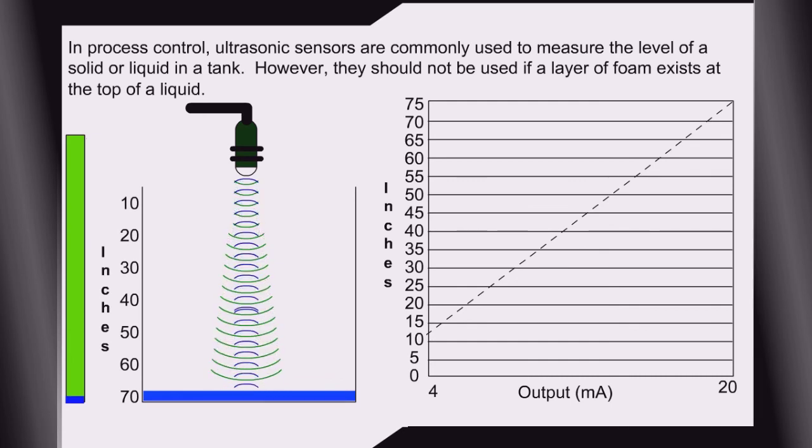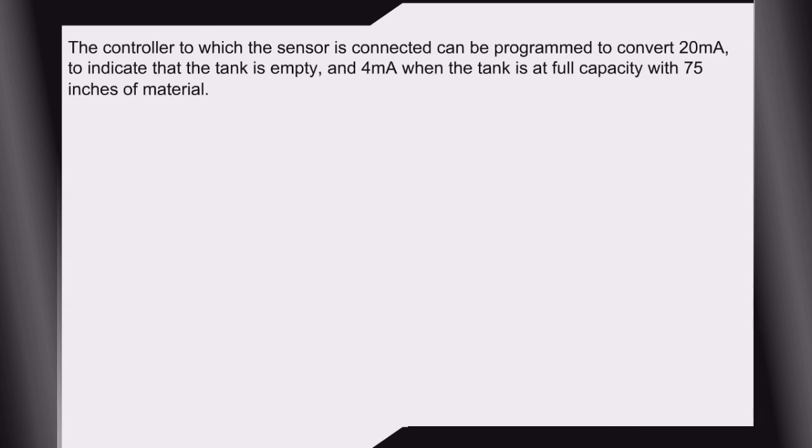The controller to which the sensor is connected can be programmed to convert 20 milliamps to indicate that the tank is empty and 4 milliamps when the tank is at full capacity with 75 inches of material.